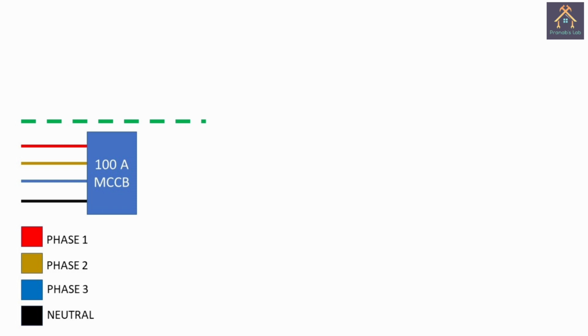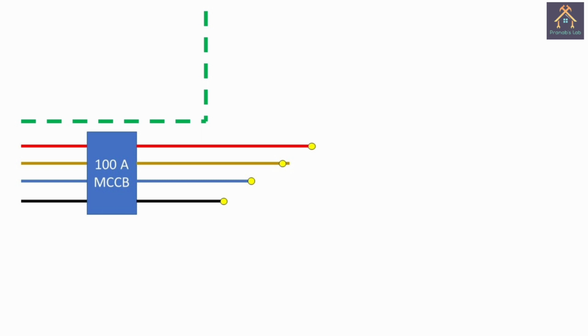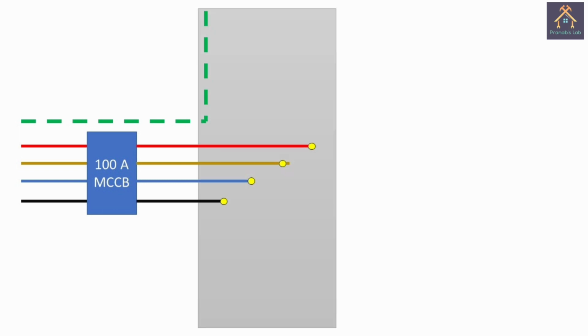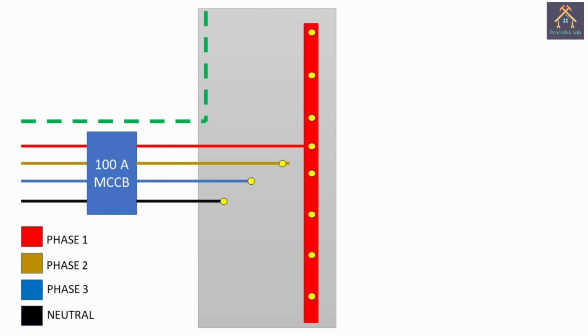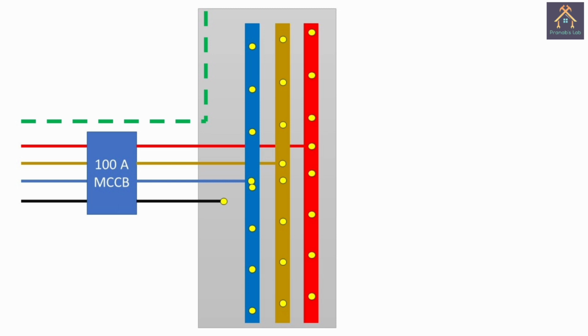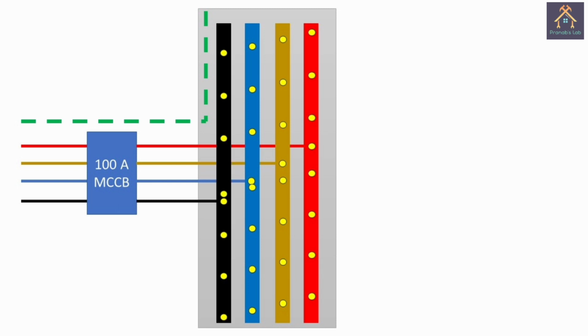The 3-phase with neutral cables are connected to the supply terminals of the MCCB, and the output load terminals from the MCCB are inserted into the busbar chamber. The red phase is connected with the red busbar, the yellow is connected with the yellow busbar, and blue is connected with the blue busbar, and the black, that means neutral, is connected with the black busbar.